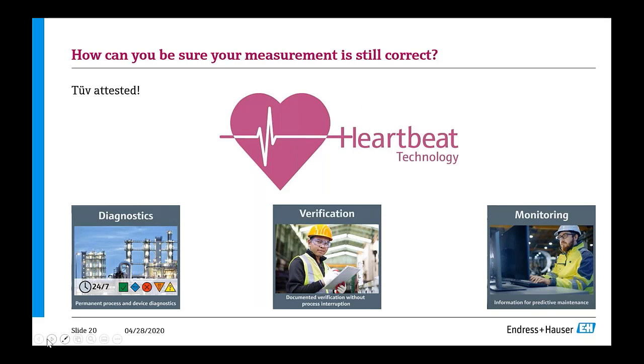So next one. Sorry, here we see a heartbeat. So I've been talking about this Heartbeat Technology. This is integrated in our devices, and both the thermal and the Coriolis meter come with Heartbeat diagnostics. That means they have error messages in line with the NAMUR recommendation NE 107. So there you see, is maintenance required? Is the device okay? Or is it out of spec, or is it broken?